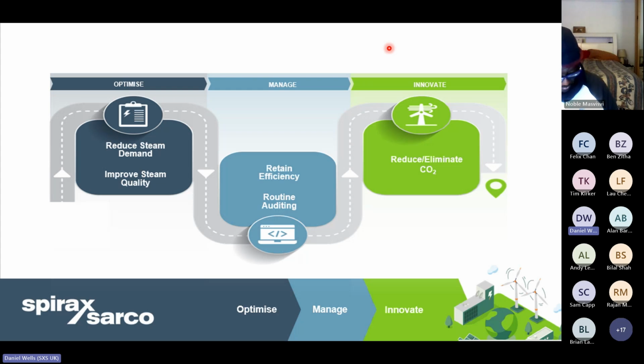It may well be that our steam boiler is producing 10,000 kilograms of steam per hour today. We may actually only require 7,000 kilograms per hour of steam at our process. So the first thing that we want to do is act upon those inefficiencies and reduce the work that the boiler has to do. It's going to be a very, very quick win and something that we can act on and realize today. The next step, we want to move forward and manage the steam system to make sure those inefficiencies don't start to creep back in.